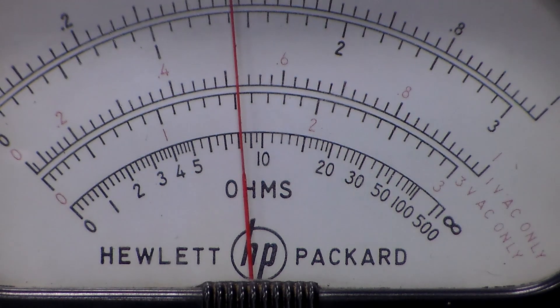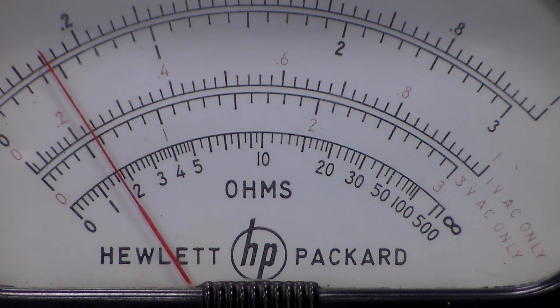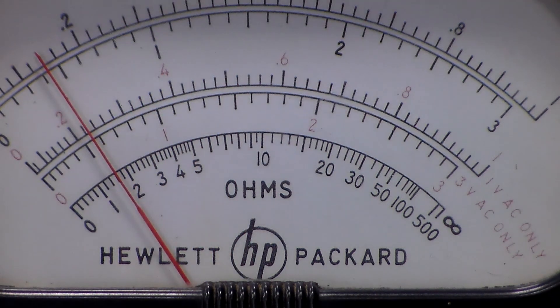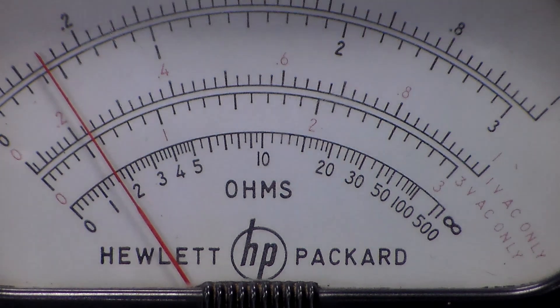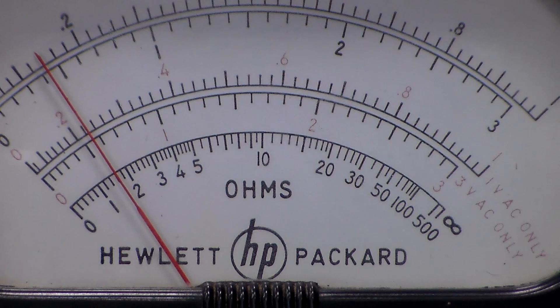If I'm doing the math right, that should be about 2% of full scale. If we go to 200 millivolts, that's about 220 as well, so once again that's still about 2% high. If we go back to 1 volt, we're still reading about 1 volt. The next step is go to the 3 volt range.